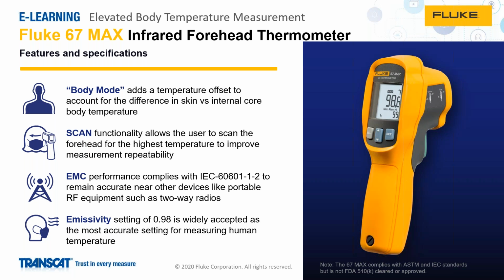We'll talk about these a little bit. It's got a body mode, as we've talked about, that adds a temperature offset to account for skin temperature being generally lower than your internal core body temperature. It's got scan functionality, which allows you to scan across the forehead to improve your measurement repeatability. EMC is tested to and complies with the IEC 60601 standard that we had discussed. And then as we've discussed at length a number of times, we do use an emissivity setting of 0.98, as that's a widely accepted value for measuring human skin.